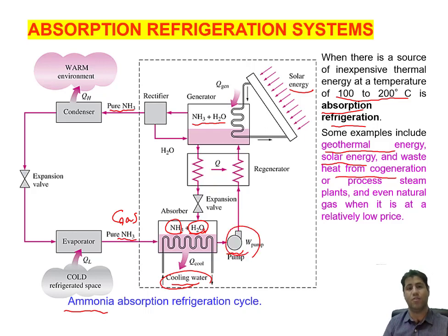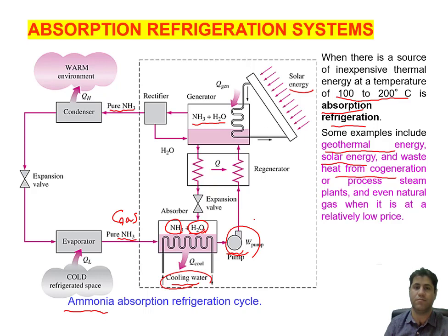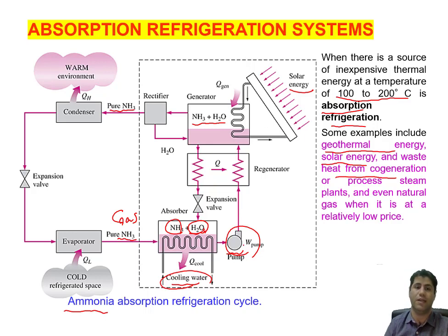The reason this absorption refrigeration system works is that instead of compressing a gas, we only transfer liquid. The required work to transfer liquid by a pump is much lower than the work required to compress gas. As we discussed in previous chapters, the required work input for any medium depends on the specific volume of the working fluid — the lower the specific volume, the lower the work input for the pump.